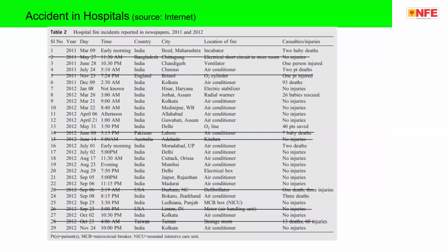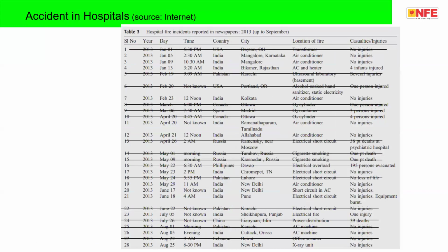In our several training programs, we were explaining repeatedly that an air conditioner with a stabilizer is a disaster. In case of a fault on the air conditioner, the stabilizer will not allow the protective device to trip. As a result, fire can happen.